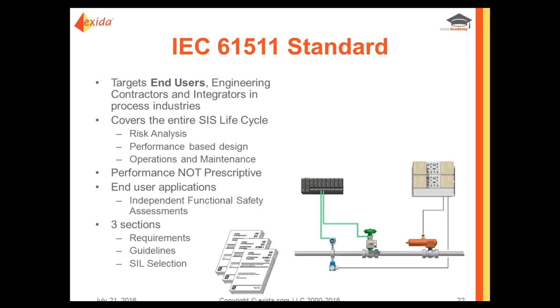The IEC 61511 standard is a user-focused standard, but it does not assign individual responsibilities. That must be done for any given project, and we'll talk about that a little bit later. There are no detailed requirements for embedded software or high-level languages like C++. It's going to refer back to IEC 61508 for that. They're very complementary of each other. It has the same life cycle and SIL concepts as IEC 61508, but IEC 61511 is more in the process industry language. There are three sections of the standard: a requirements section, a guideline section, and a SIL selection section.